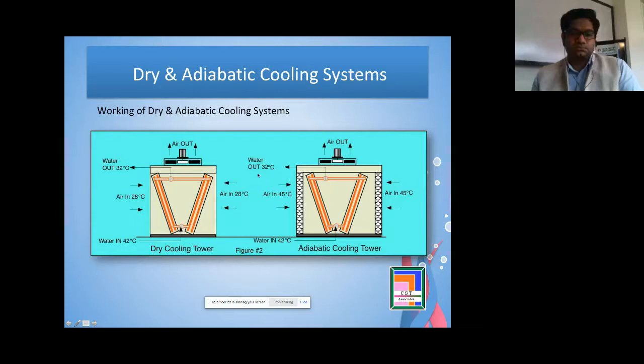So what happens is, when the water temperature going in is 42 degrees and our expected temperature is 32, and our ambient goes to 45 degrees centigrade, the water starts spraying on these pads and it reduces the dry bulb temperature. When the ambient temperature is 45 degrees centigrade, our expected wet bulb temperature will be almost 29 or 28 degrees centigrade, depending on the area and what kind of humidity is there. Let's say 29 degrees centigrade is established at this point. When this saturated 29 degree air passes over the fin surface heat exchanger, it drops the water temperature from 42 to 32 degrees centigrade.